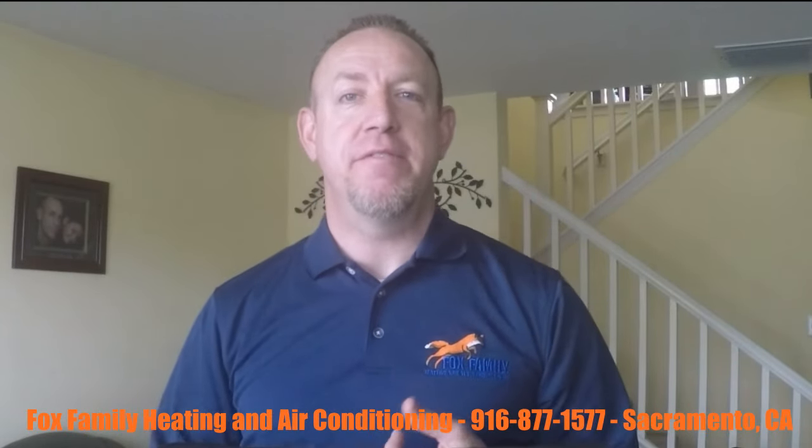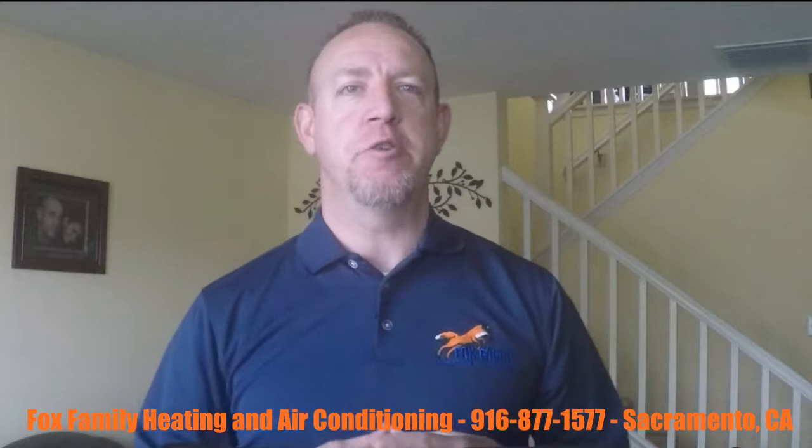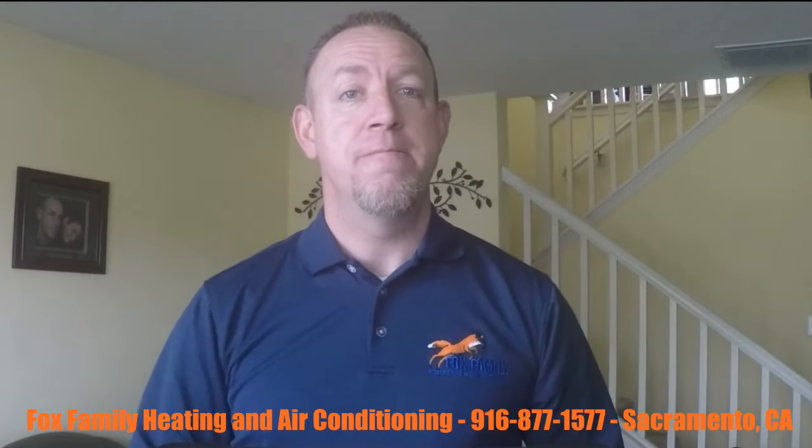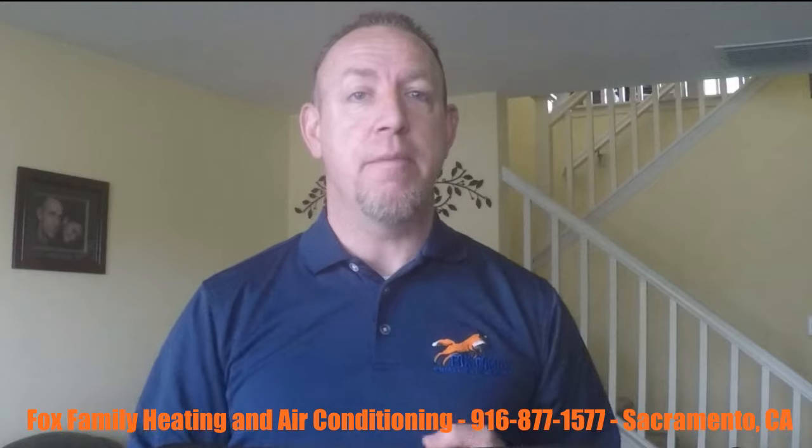We assess and evaluate the following things at the air handler: manufacture date, the door safety switch, and the temperature difference of the air coming into your system and coming out of your system. We want that difference between 18 and 22 degrees. Your blower capacitor rating and the actual value of it. We're checking for a balanced blower wheel for efficiency. We're checking your blower assembly for cleanliness, for longevity of life and efficiency. Primary drain lines, so that they get purged with nitrogen for proper operation.